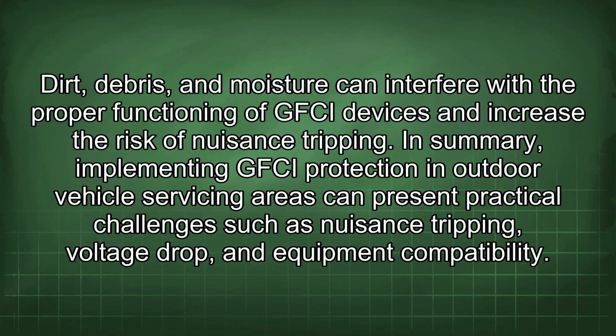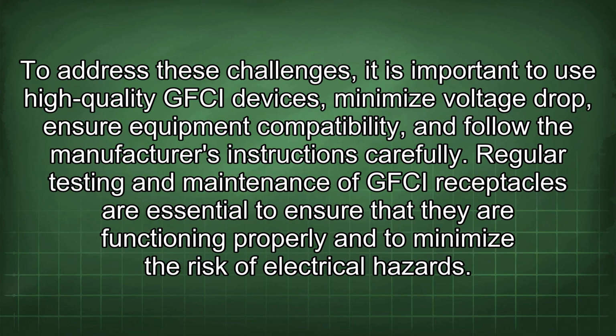In summary, implementing GFCI protection in outdoor vehicle servicing areas can present practical challenges such as nuisance tripping, voltage drop, and equipment compatibility. To address these challenges, it is important to use high-quality GFCI devices, minimize voltage drop, ensure equipment compatibility, and follow the manufacturer's instructions carefully.